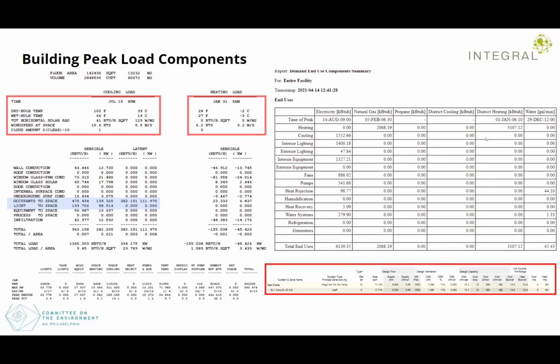And likewise, you want to look at the demand, right? The total demand for cooling, interior lighting, receptacles, for example. These are very simple calculations because they are input as watts per square foot times the number of hours it gets utilized and the diversity that's applied to it. So these are very straightforward calculations. They do get complicated when you have sophisticated lighting controls, but generally it is a good gut check to look at this and say, does this make sense?